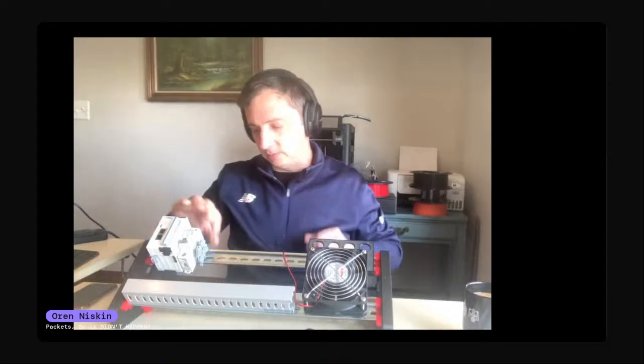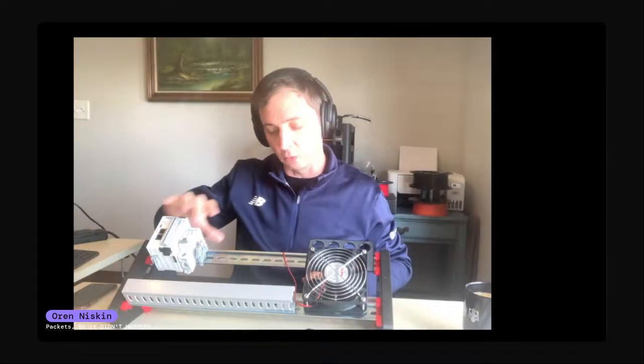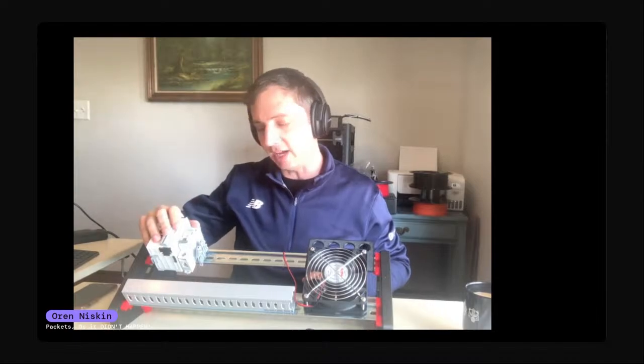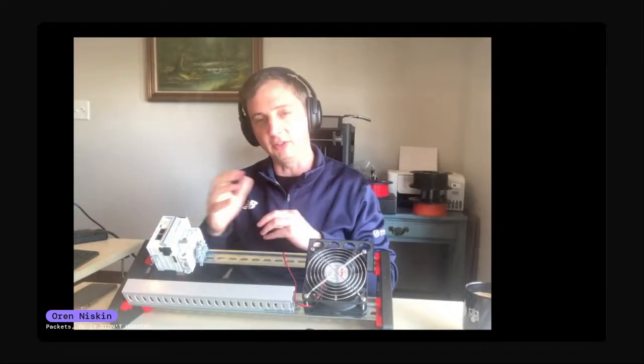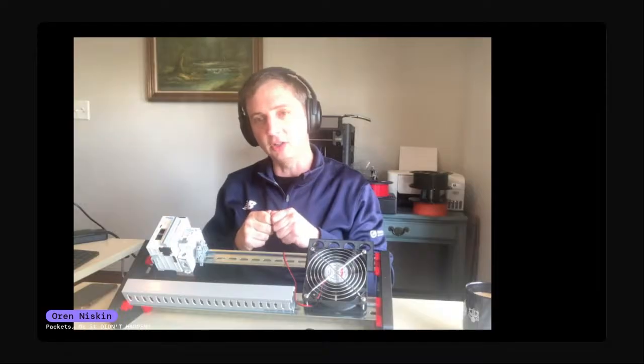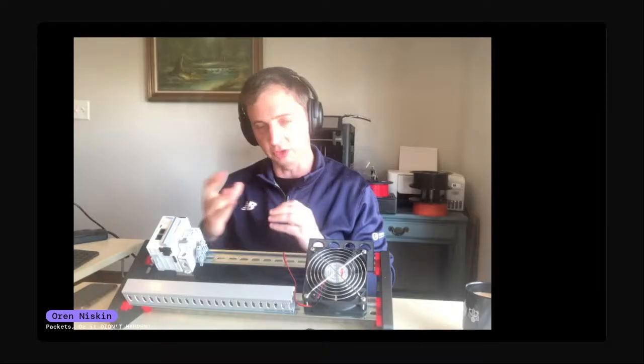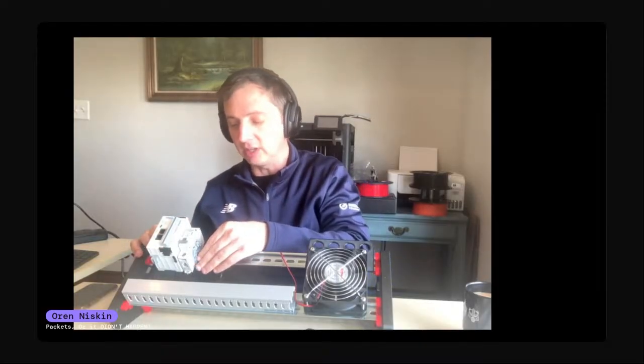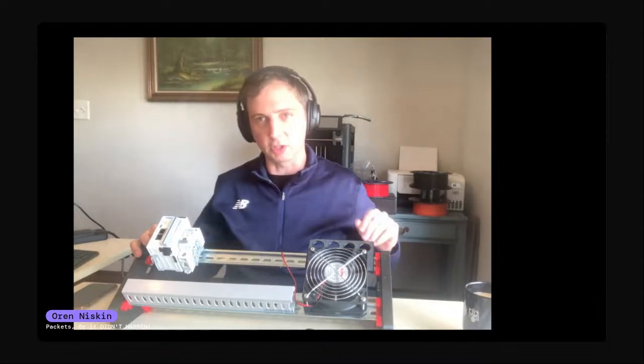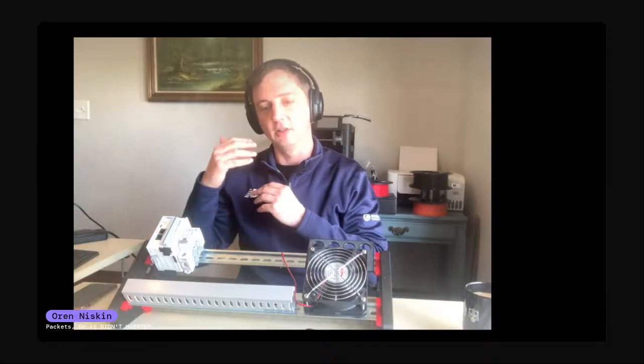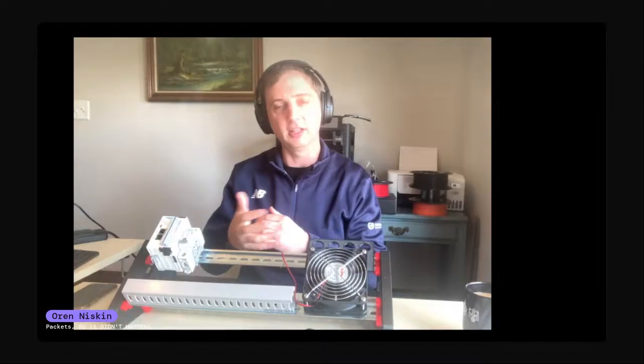You also want to make sure the circuit breaker is rated for what the wires are allowed to carry — that's the main point. A lot of people think a circuit breaker is meant to protect equipment like PLCs, but it's actually meant to protect your wiring. In your house, you have certain size wiring with a circuit breaker tied to that size. If there's a malfunction or a short, it doesn't cause so much heat in the wire that it catches fire and burns your house down. A lot of places have burned down from not having the right circuit breaker size for their wires, which allows wires to catch fire, and that's a big problem.